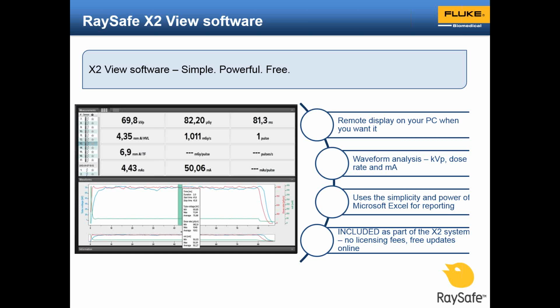Service and calibration is a necessity with any medical test equipment, and the RaySafe X2 was designed with service in mind. Calibrations are held within each individual sensor, so logistically only the sensor itself needs to be returned for calibration. If you work in a large group or service organization with multiple systems, sensors can always be swapped between base units without a problem. And if you have multiple sensors, this means zero downtime for your organization.